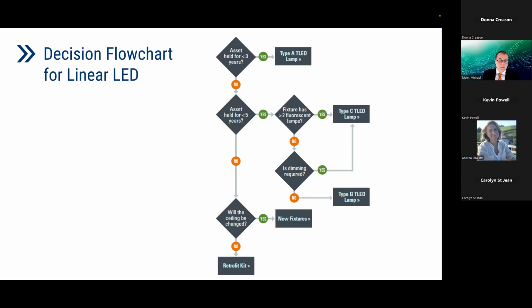Someone asked why a retrofit kit and a new fixture, both having electronic drivers and LED arrays, would differ in life. The new fixture has a slightly longer life because the whole fixture is designed to accommodate that LED system through heat management. In a retrofit kit, which I'm a big fan of, you're taking the existing fluorescent fixture, pulling out the optical assembly and electrical guts, and putting the LED array in. You're still dealing with how that shell manages heat, so it's not a one-for-one wholesale design of LEDs.